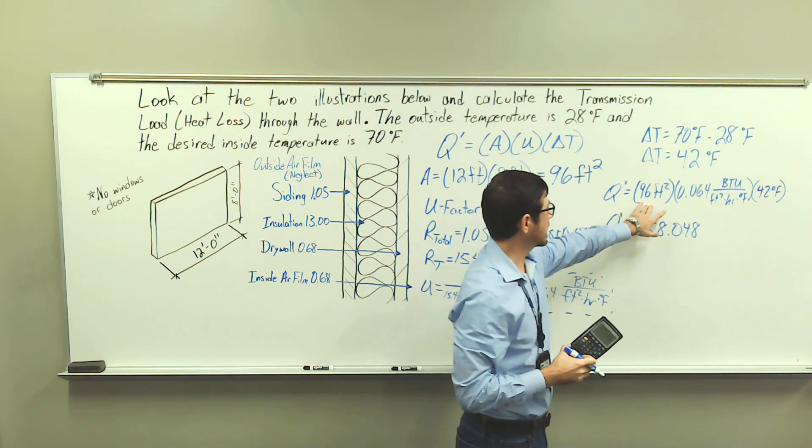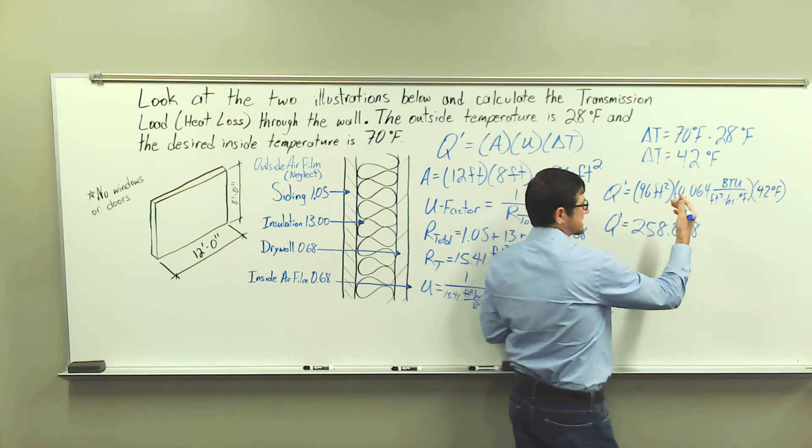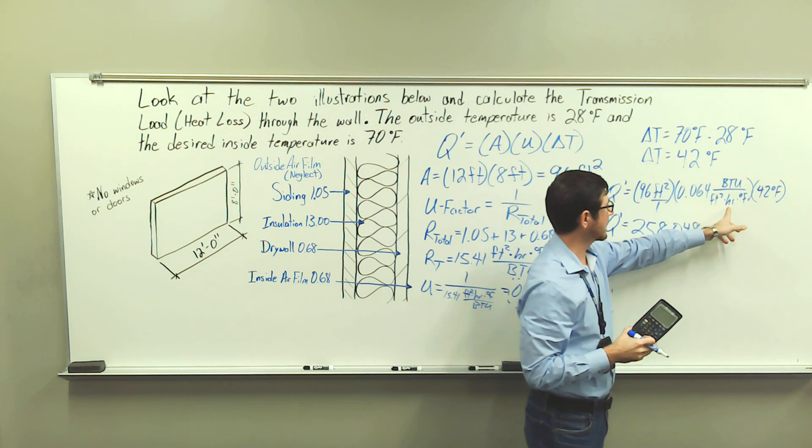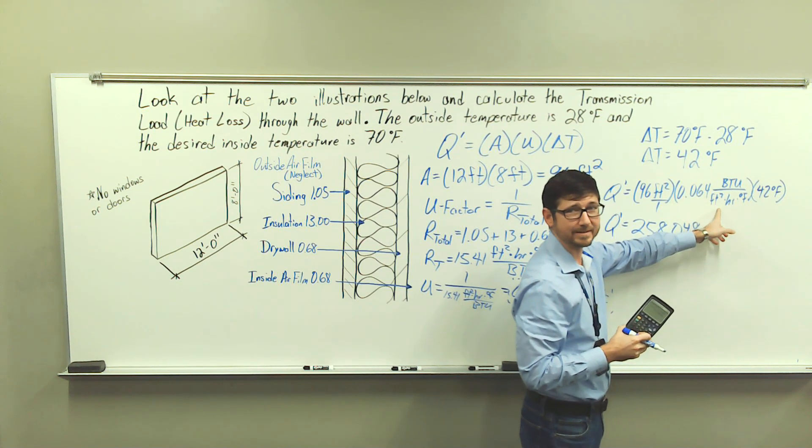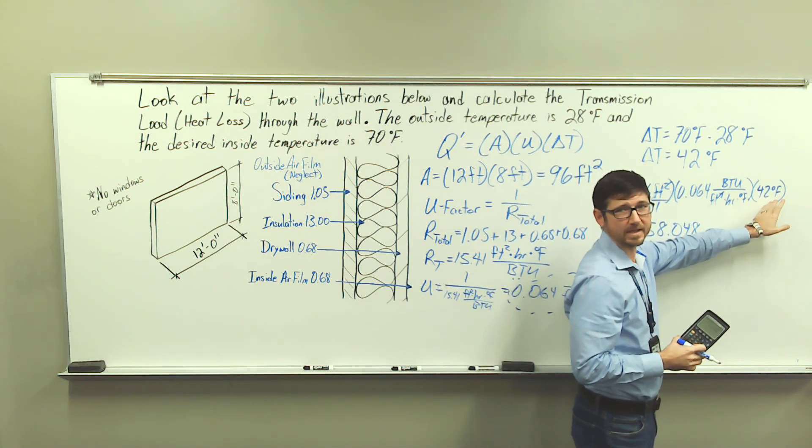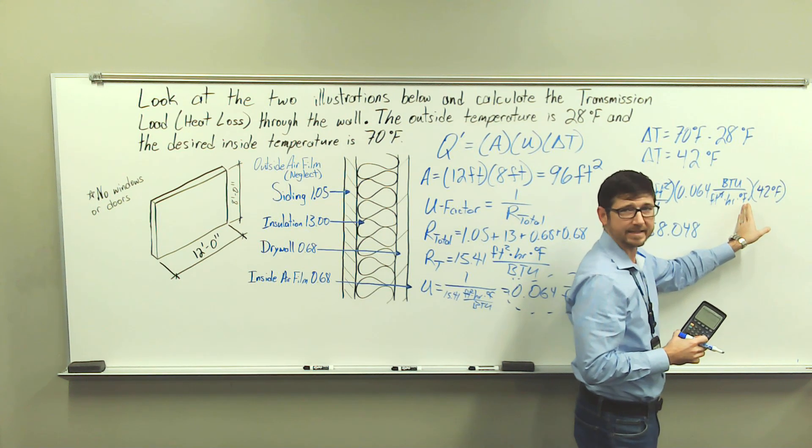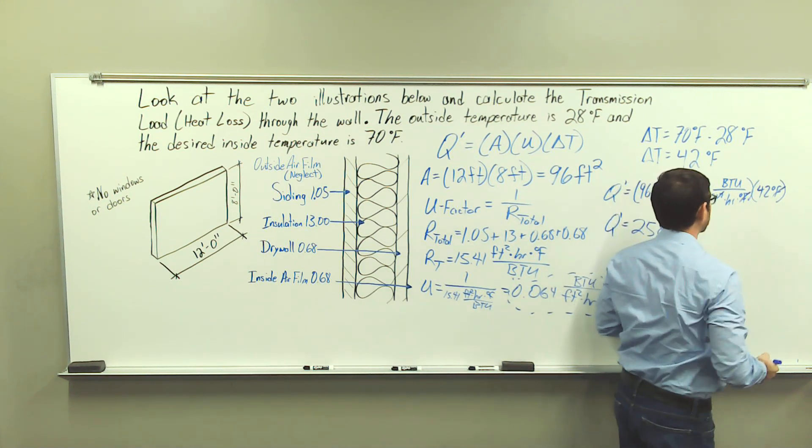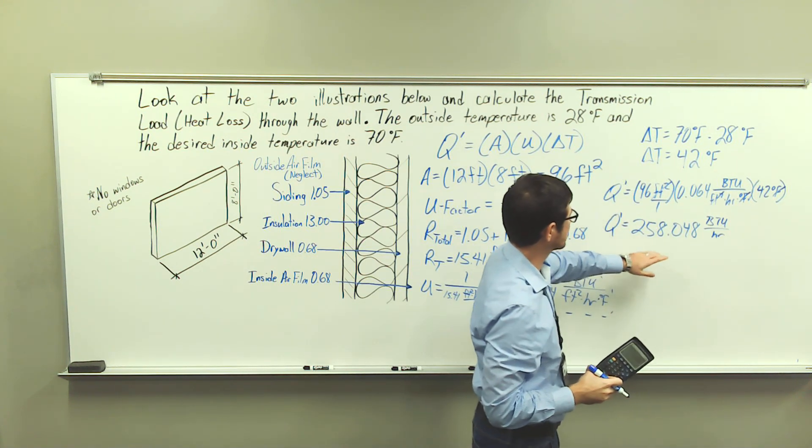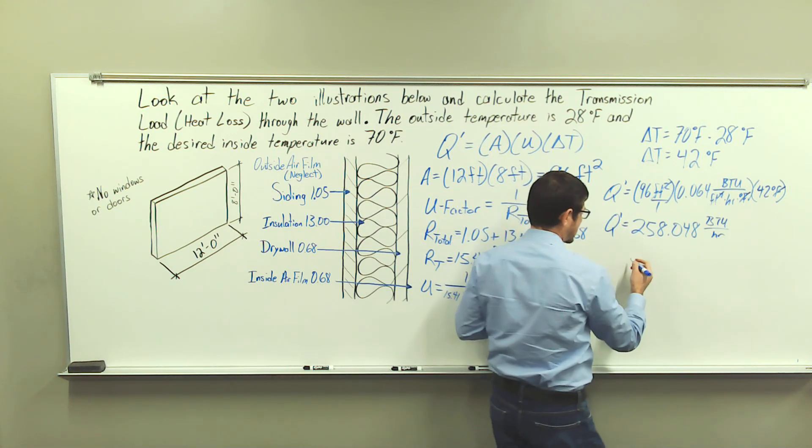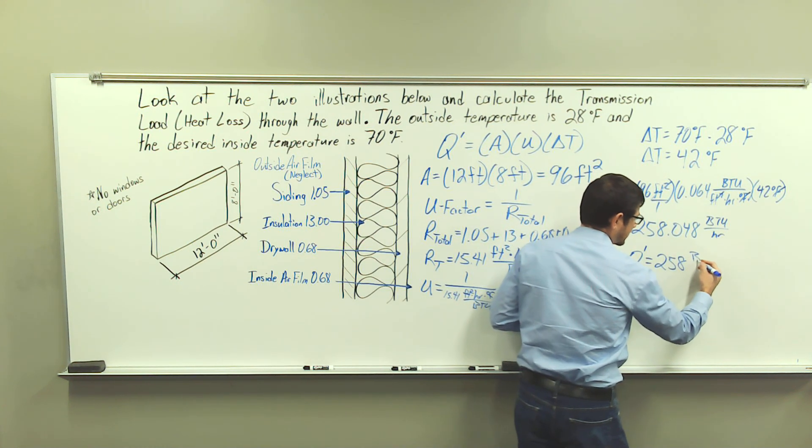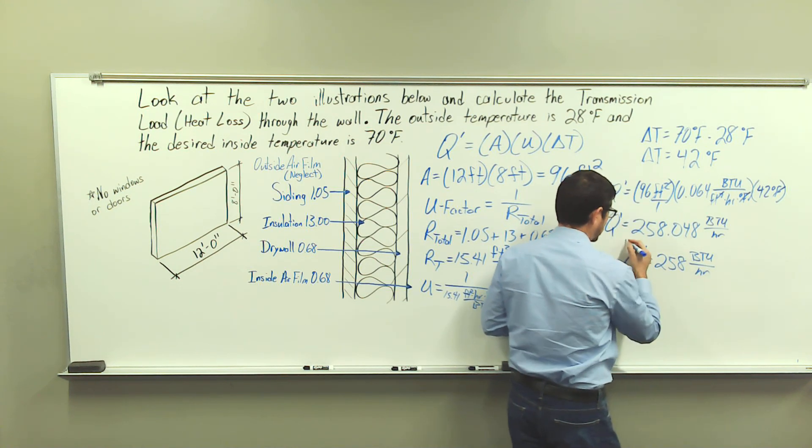All right, we have foot squared, and we can also write this algebraically. This is foot squared over 1, so it's in the numerator, and we're multiplying it here. And I have foot squared in the denominator, so foot squared is going to cancel. And then we have degrees Fahrenheit here in the numerator and Fahrenheit in the denominator, so these will cancel. And this gives me BTUs per hour. And I'm just going to go ahead and round to the ones place here. So my heat loss, Q prime, is equal to 258 British thermal units per hour.